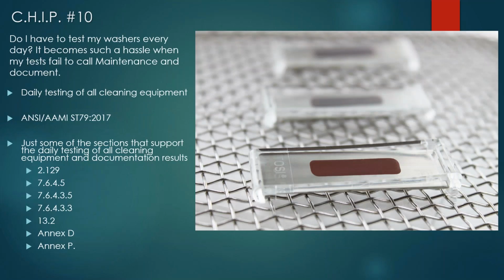Chip tip number 10, do I have to test my washer every day? It becomes such a hassle when my tests fail to call maintenance and have it documented. Daily testing is recommended, especially in ST79. The pieces of equipment that we're using are very crucial to producing acceptable patient care equipment, right? To producing clean equipment for the staff to check and then sterilize. We know there's no such thing as sterile dirt. That doesn't exist. So knowing that my machine is adequately removing soil is very important. And as you can see, it shows up in section 2, section 7, section 13, and 2 annexes of ST79, really talking about just how important testing of your equipment is.